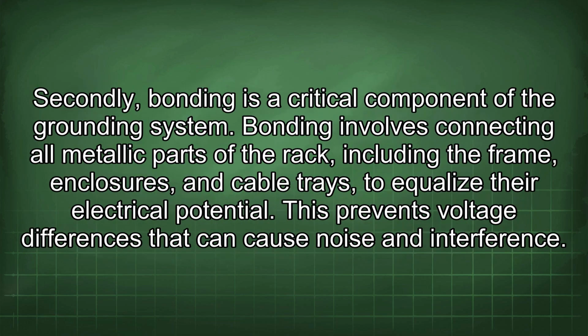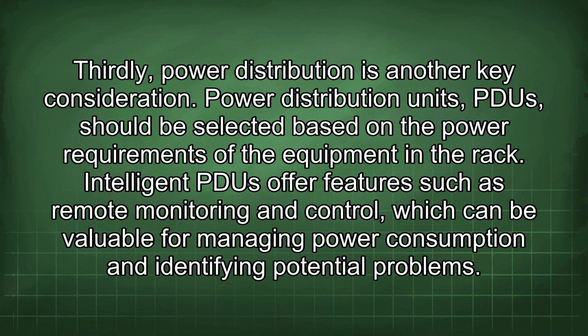Secondly, bonding is a critical component of the grounding system. Bonding involves connecting all metallic parts of the rack, including the frame, enclosures, and cable trays to equalize their electrical potential. This prevents voltage differences that can cause noise and interference. Thirdly, power distribution is another key consideration.